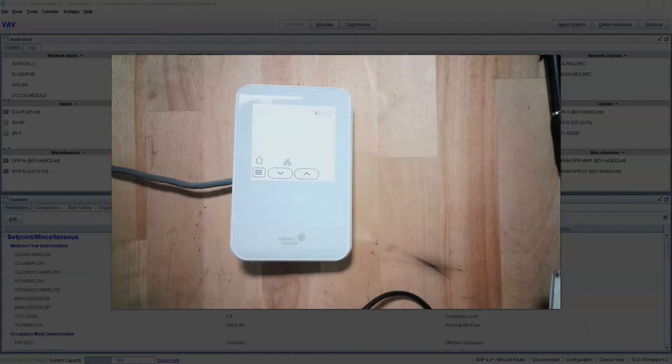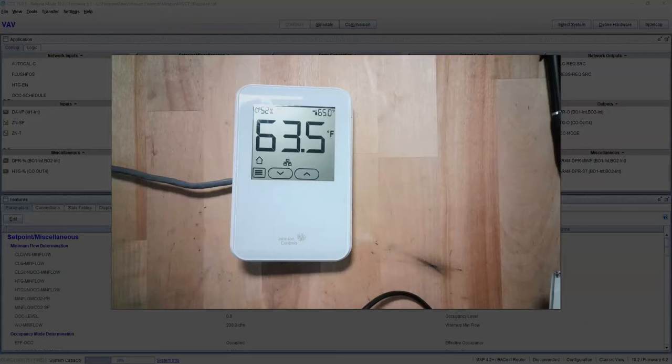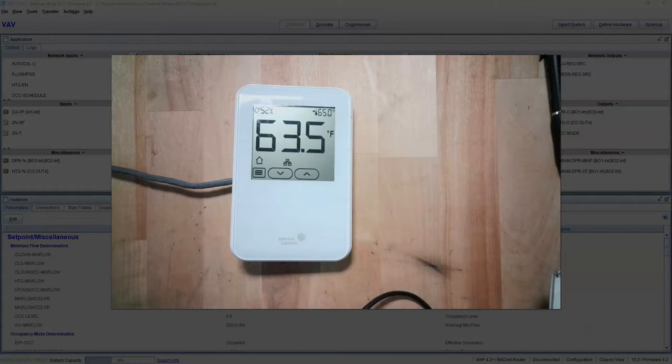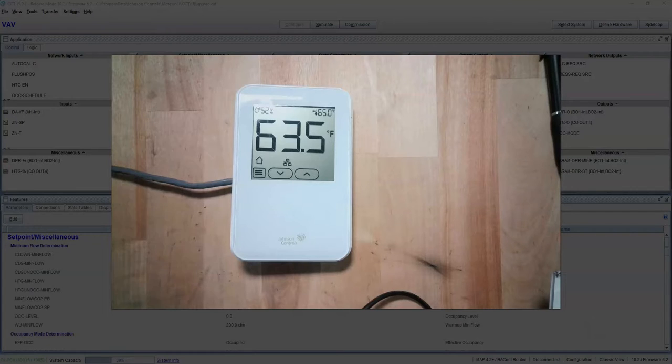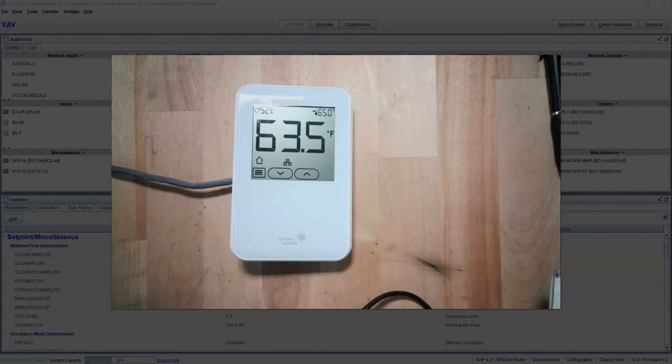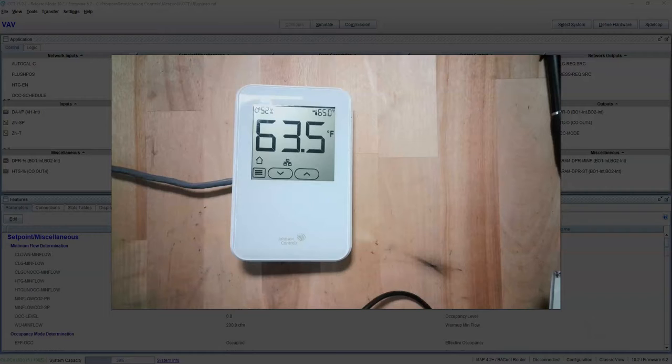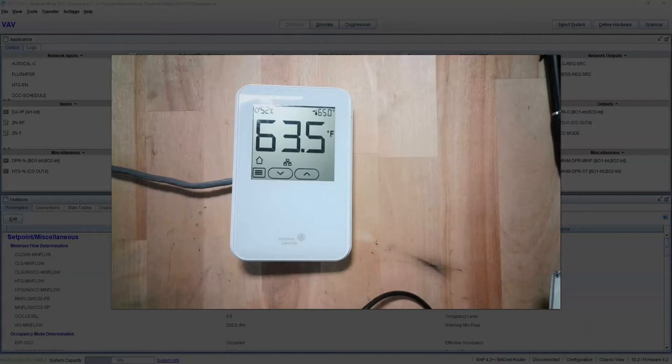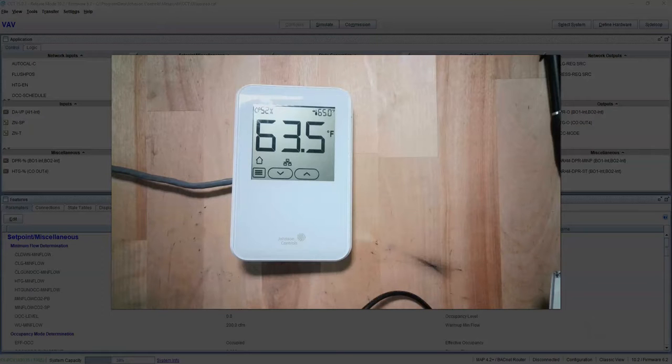Relative would be us giving the controller a network setpoint, let's say 70 degrees, and then the operator has adjustment up or down from that 70 degrees. They don't really know the setpoint, but they know they can go up or down from the setpoint. They can make it warmer, they can make it cooler.